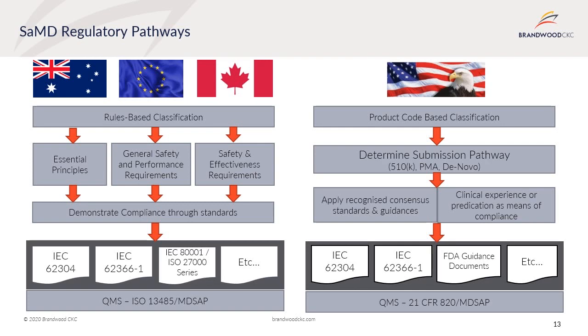The US approach is somewhat different in that the classification is based on product codes contained in FDA's product code catalogue. The classification will then determine the submission pathway — either a pre-market notification (510k), pre-market approval (PMA), or de novo if a product code does not exist. The means of compliance is usually by using clinical experience, evidence, trials, and demonstrating substantial equivalence through predication. FDA also recognizes consensus standards which may be used to demonstrate compliance. For all jurisdictions, the manufacturer is expected to establish a quality management system based on ISO 13485 or MDSAP in the GHTF countries, and 21 CFR 820 or MDSAP in the US.